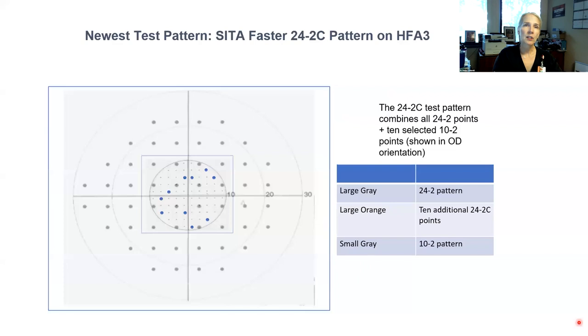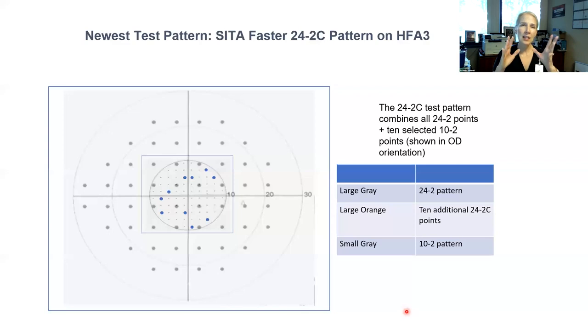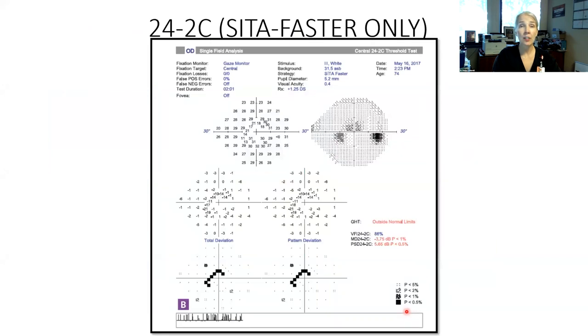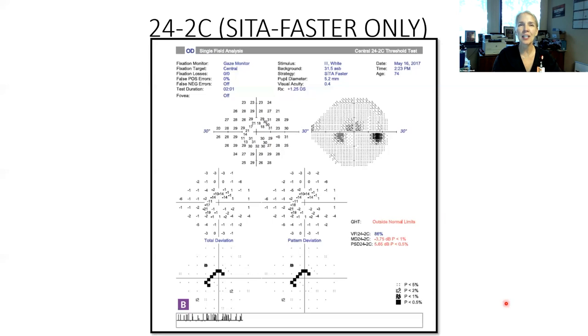There is a new test pattern on the Humphrey Field Analyzer called the 24-2C pattern — the C stands for central. It is a standard 24-2 test with five additional test points in the central 10 degrees above the horizontal midline and five below, represented by those blue points. This is a hybrid test between a 24-2 and a 10-2, allowing us to sample a little more of those macular ganglion cells without having to run two separate tests. I have this test but don't use it frequently — it looks a little strange when the printout comes out because of those additional test points.